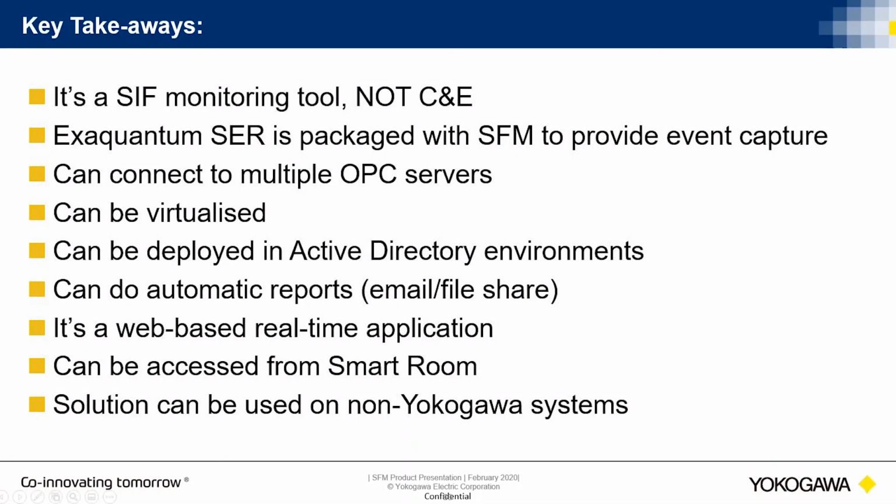I have only some key takeaways from the SFM. So we did mention that it's a SIF monitoring tool, not cause and effect. However, there is nothing stopping you from putting extra elements into it for specific monitoring purposes. Like you've seen, I've put, instead of 3, 6 valves in my SIF, but it's not a SIF function. It's not specifically a SIF. It's just monitoring.